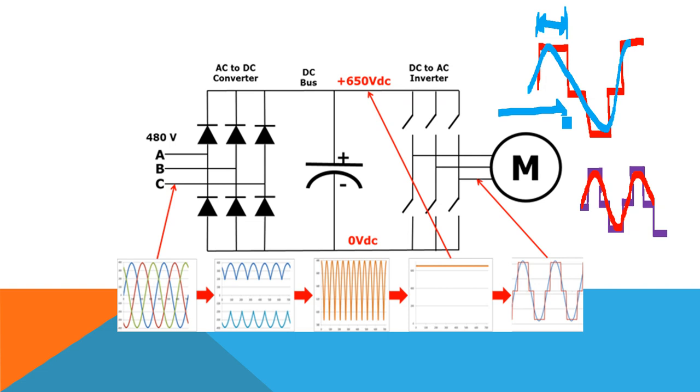But when it is operating on an inverter, the motor may create a humming because it is not a perfect sine wave. If the sine wave is not perfect, there will be some flux imbalance in the motor and it will give humming.